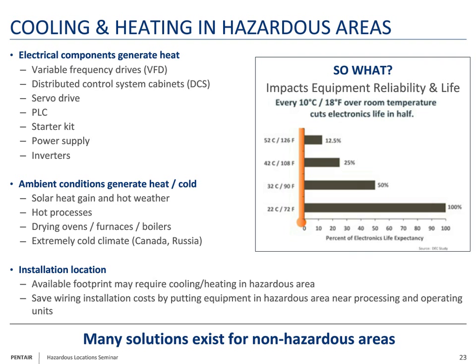Cooling and heating in hazardous areas. So why would you need to cool or heat? Well, heat really impacts equipment reliability and life. For every 10 degrees Celsius, or 18 degrees Fahrenheit, you cut electronics life in half if you go over room temperature. So you may want to protect some really critical equipment like a variable frequency drive, a distributed control system, or a critical PLC controlling a processing unit or process equipment. You may want to protect that and give it long-term longevity so you don't have failures in the field.